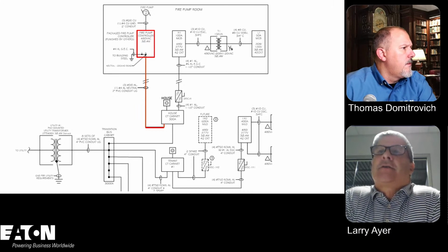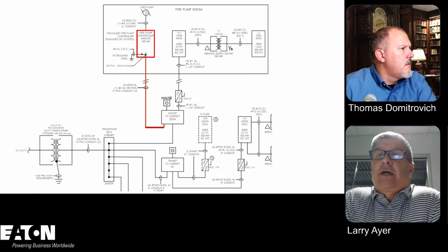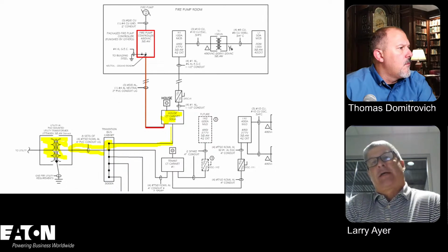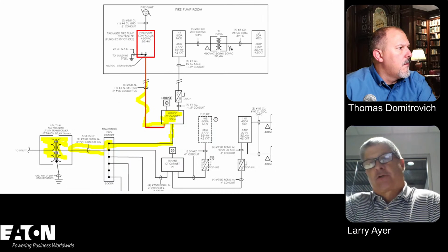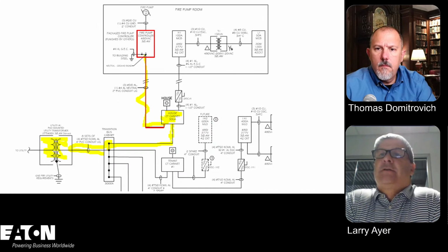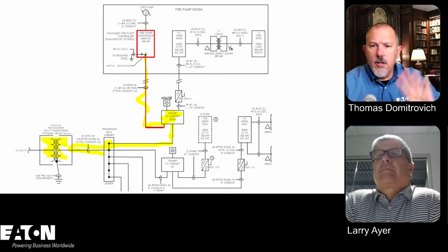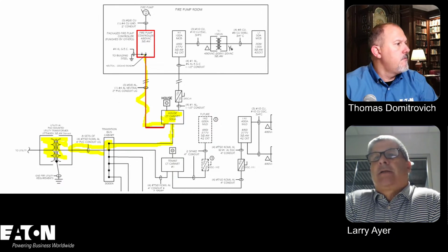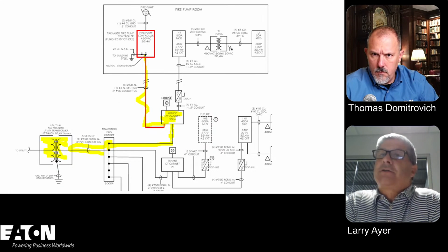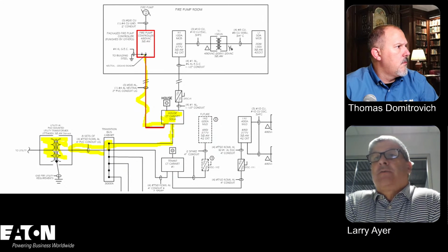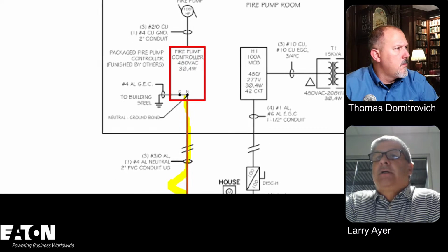So this one here, some people send me these drawings to look at, and this one is tapped off the CT. Even though you have your utility transformer outside and you go through a couple of different cabinets, you still keep tapping off. There's no overcurrent protection there, and you run that straight from that meter enclosure all the way over to your fire pump controller. Yep, so those are service conductors. That needs to be a service entrance rated controller. Those wires need to be sized for 125% of the full amp capacity of the fire pump and any associated motors that may be tapped off of that. And all of your bonding and protection is going to be standard 230 wiring. Correct. And even though it's a 3-wire motor, you still have to take the neutral to that controller. These are service conductors, so they're unprotected, and you have to route them outside the building to get to that fire pump controller.